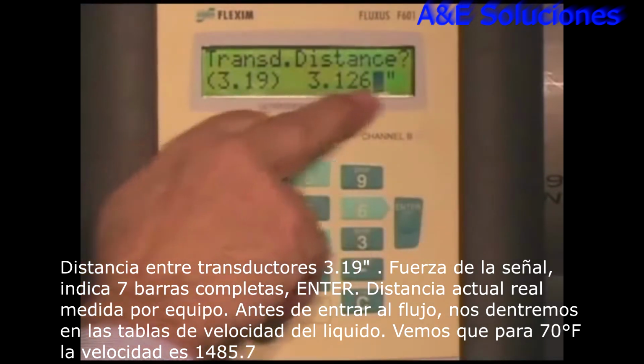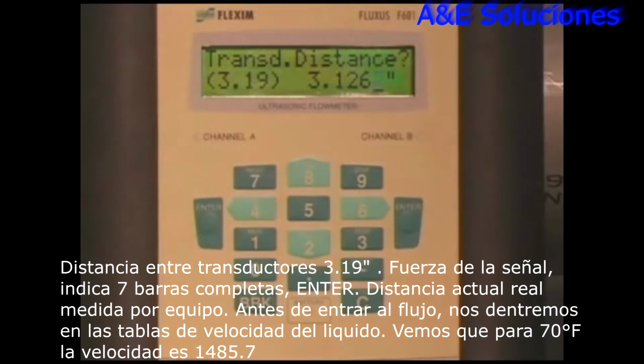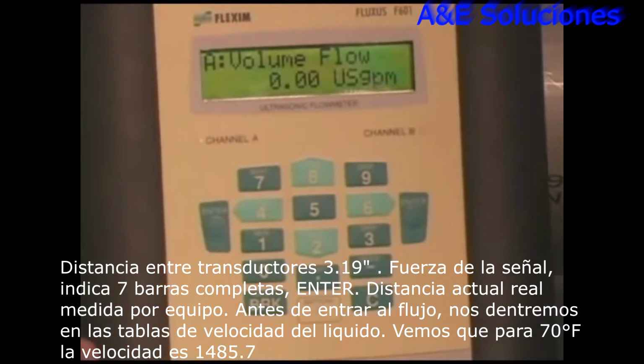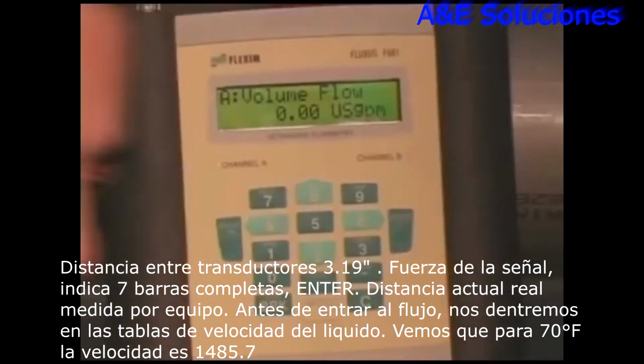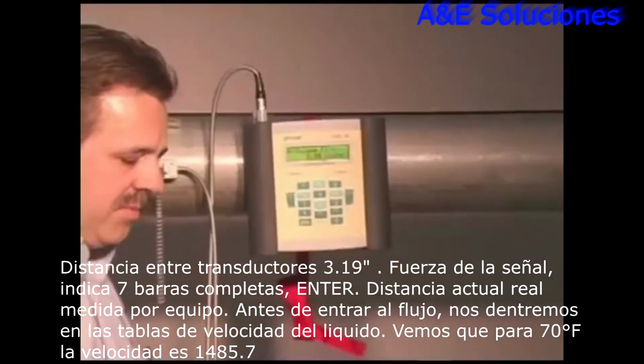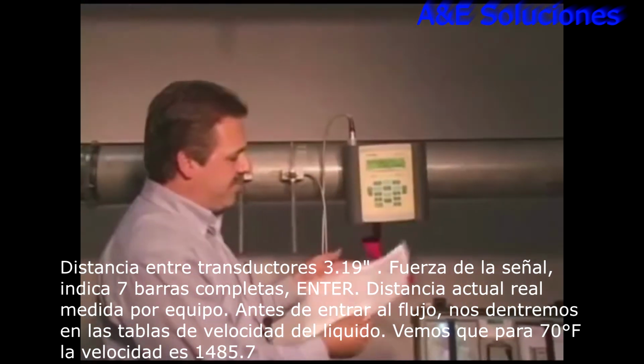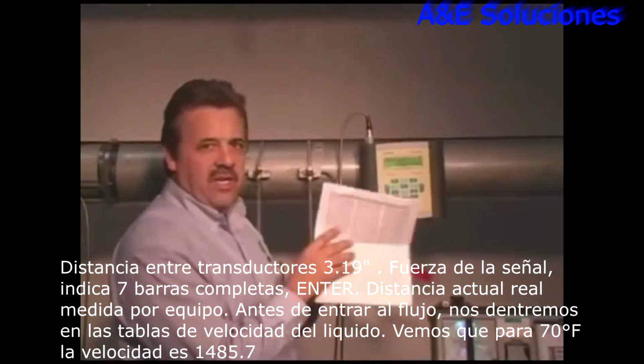My actual distance I put the meter at, 3.125, enter. And I'm reading flow. Now before I show you the flow, I just want to show you one more thing. Now this diagnostic screen, the diagnostic that we call sound speed or sound velocity, the sound speed of the liquid. Now one of the things we put in with the portable meter along with the pipe tables is you'll see a chart here for sound speed.